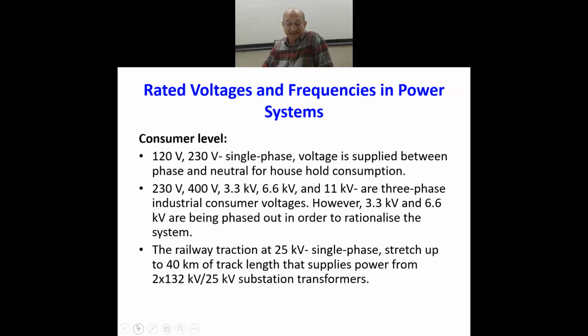And these voltage levels slowly have been phased out, because you can imagine the power handling capability is proportional to the square of the voltage. So a 3.3 kV system, and an 11 kV or 6.6 kV system would handle very little power, and the load is continuously increasing. So 11 kV is one of the standards of the power distribution level, and then 33 kV is also a distribution level, which can also transmit the power to short distances.